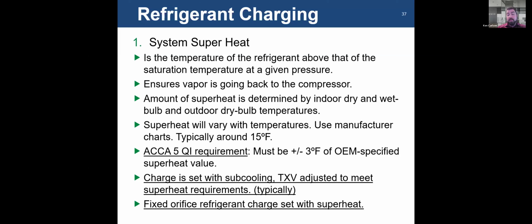Typically, your charge is actually set with subcooling. Your TXV would be adjusted to reach your superheat requirement. Typically, if you have a fixed orifice system, right? You don't have a TXV, you've got a piston instead, a fixed orifice, you actually would set your charge with superheat and superheat alone. You verify your subcooling as a reference, but you would actually set to superheat.